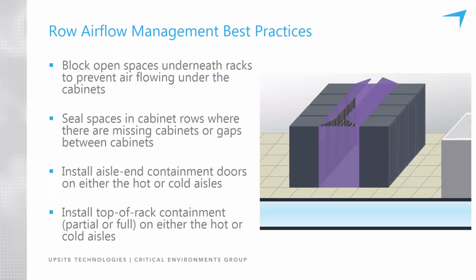So these 4 bullets represent the key best practices for row or aisle level airflow management. We'll get into much greater detail on each of these on some of the subsequent slides, but I wanted to do a quick overview right now. So the first thing is blocking off open spaces under the racks. Cabinets are often delivered with casters and levelers to aid with initial deployment. So if your cabinets have casters and levelers, then by default, you'll end up with a gap between the floor and the bottom of the rack. And blocking this gap is what we're referring to here.